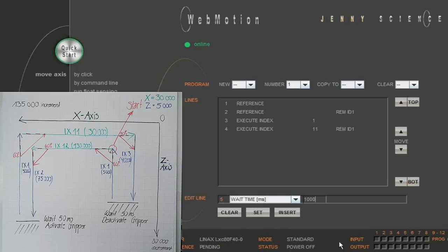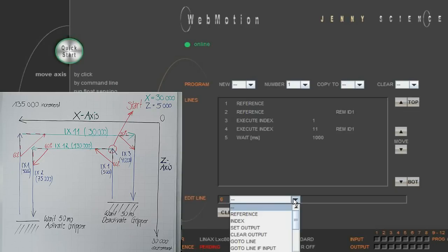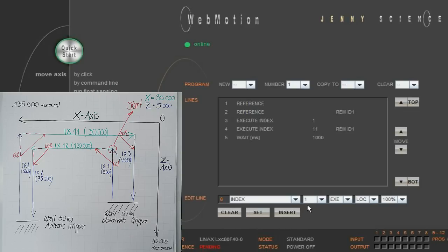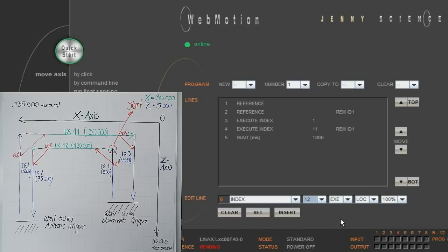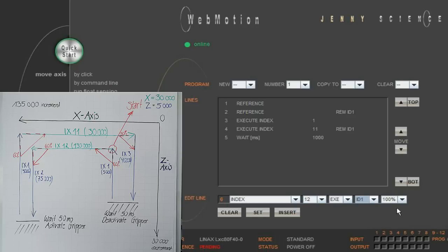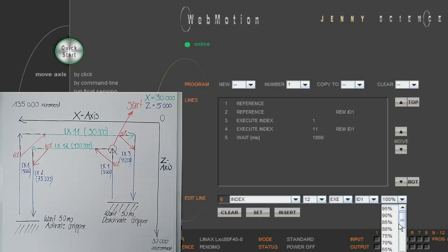Now we are ready to program the actual pick and place process. We set index 12 for our slave controller that orders the X axis to move to 130,000 increments. With the 60% we indicate that after 60% of the distance of index 12, the program begins the next line, while at the same time index 12 continues to its end.